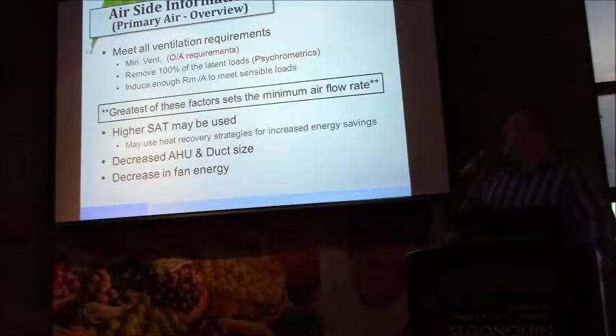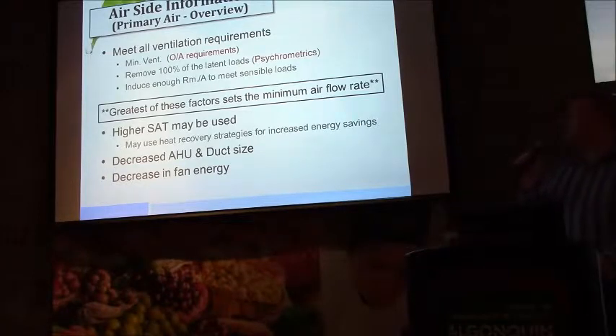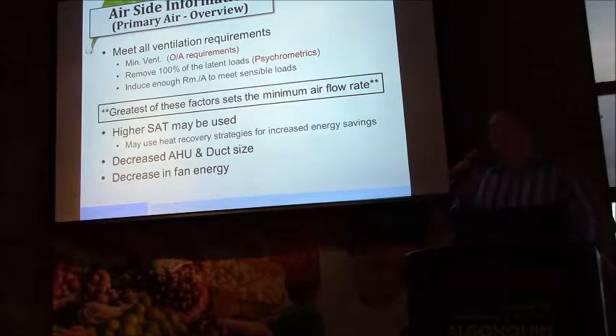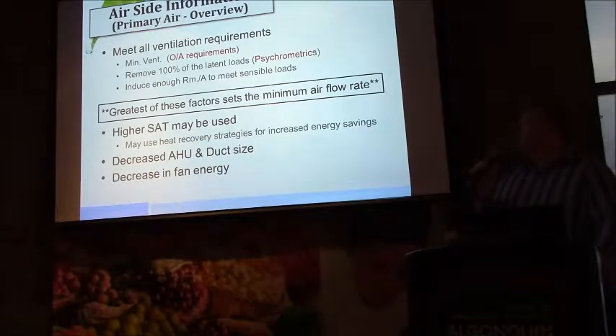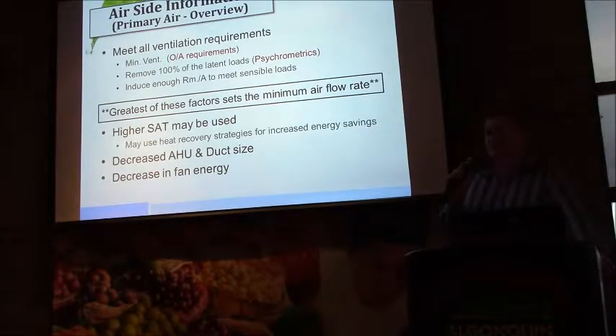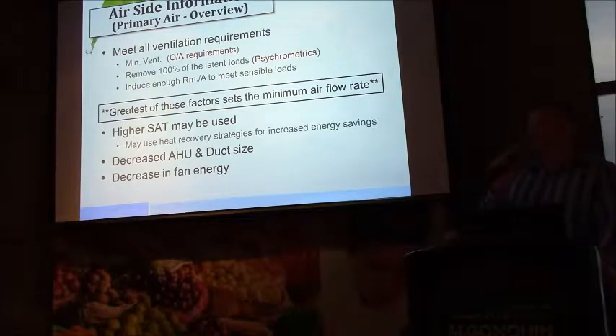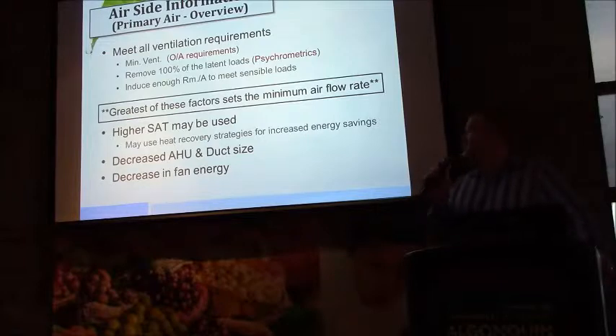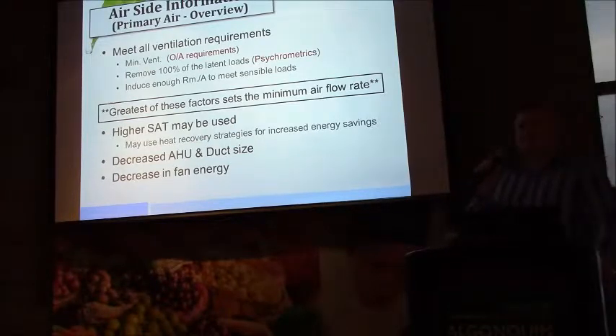The other side of the equation, in terms of how much mass flow of primary air is needed to offset the latent load in the space, is how humid we allow the space to be designed to. And the difference, the separation between the dew point of the primary air and the dew point of the room design condition, fundamentally drives the mass flow rate that's required for the second element, and that is the one with which to dehumidify the space. The third is the volume of air that we need to introduce to the beam itself to create induction.